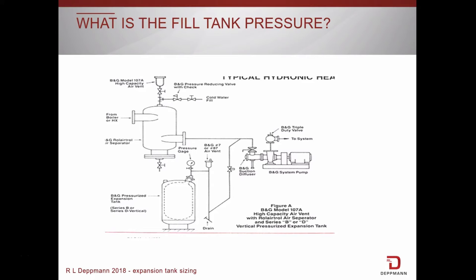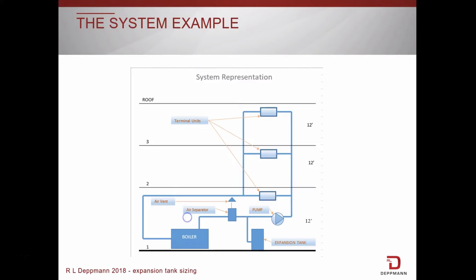Here is an example of a hydronic system. The bladder expansion tank shown here will be charged with air on the outside of the bladder. That air charge pressure will be equal to the cold fill pressure in the tank.